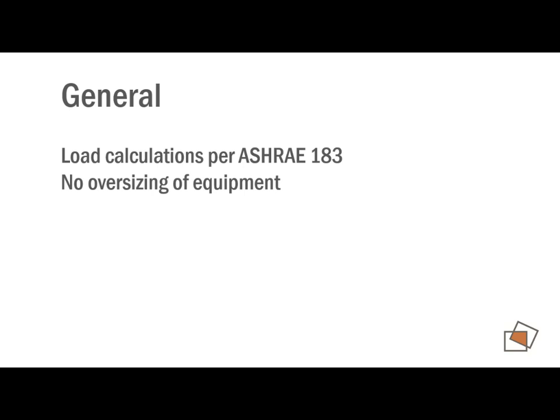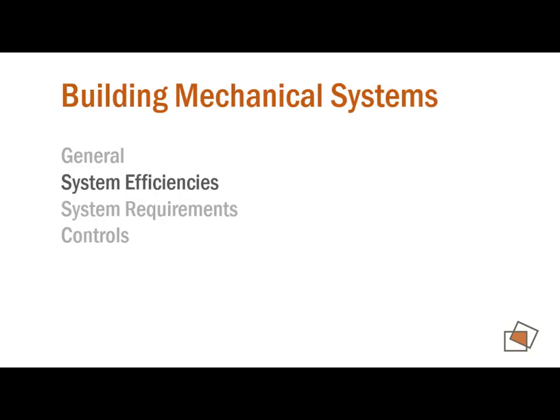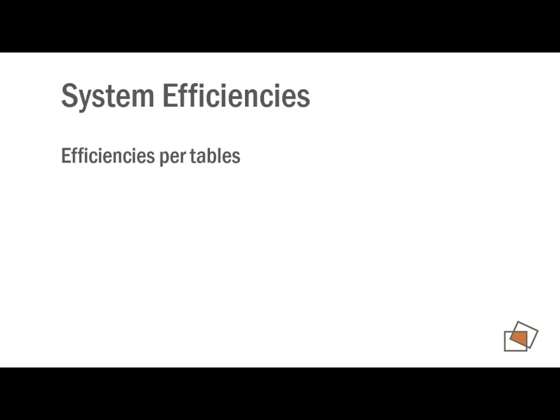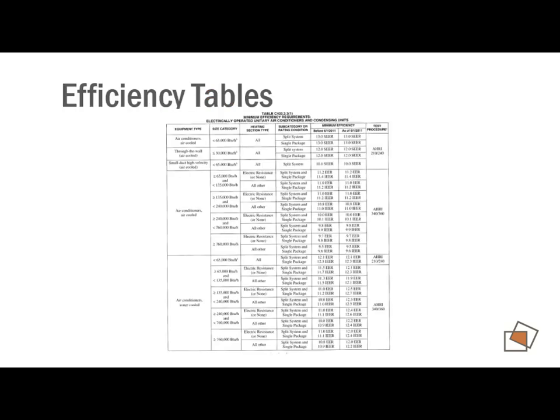So if you follow your load calculations through by this method, then you're going to be compliant with the code, and you should have a right size system that'll perform for what you're doing. Remember, they told us also the thermostat set points we have to plug in when we're doing that sizing. So then we get into the system efficiencies of the mechanical code, and we get more tables, and there are pages and pages of tables. So I've copied them all here so we can look through them all.